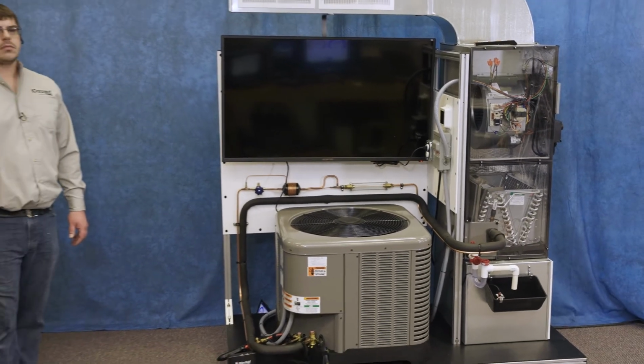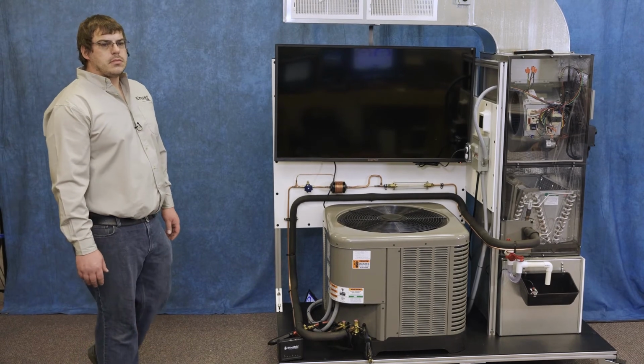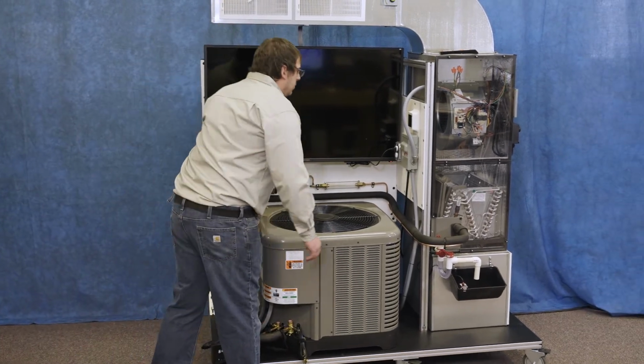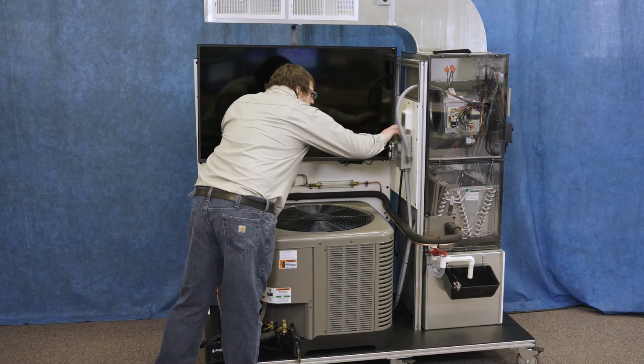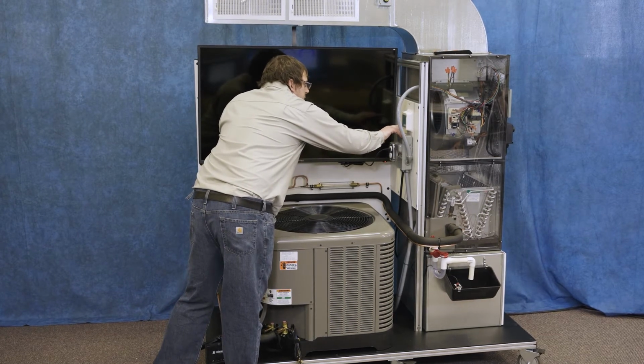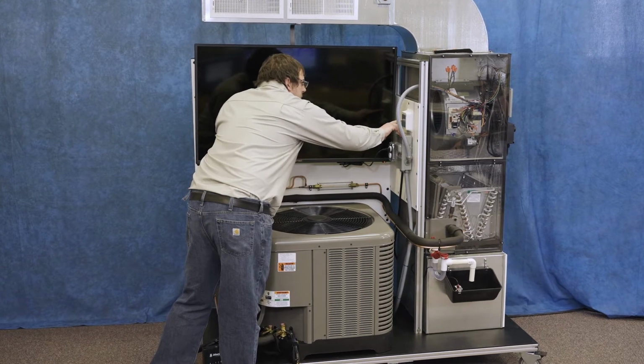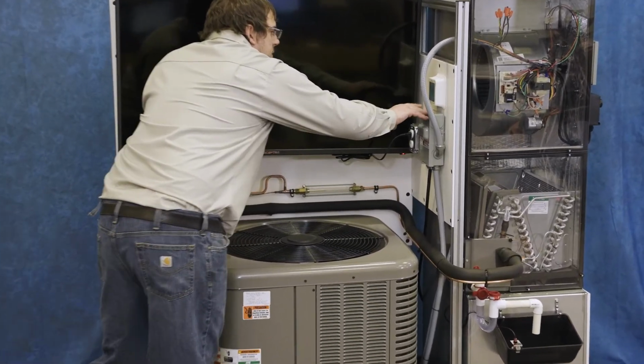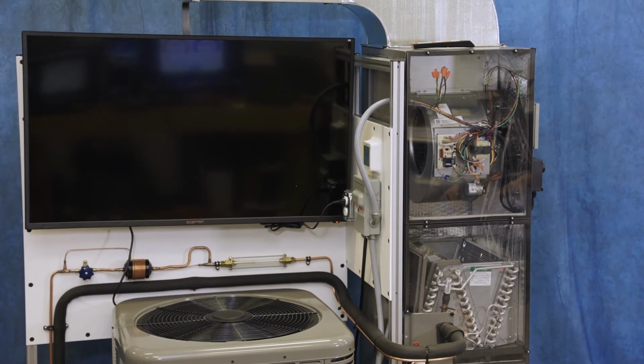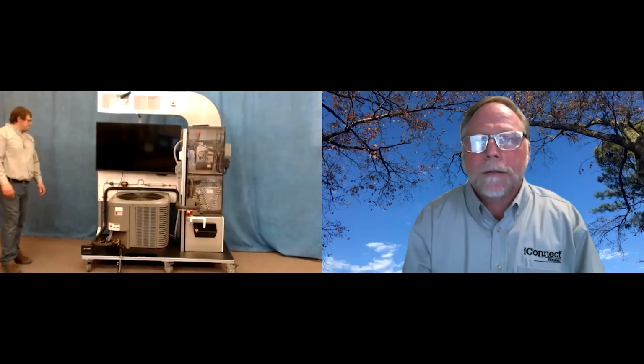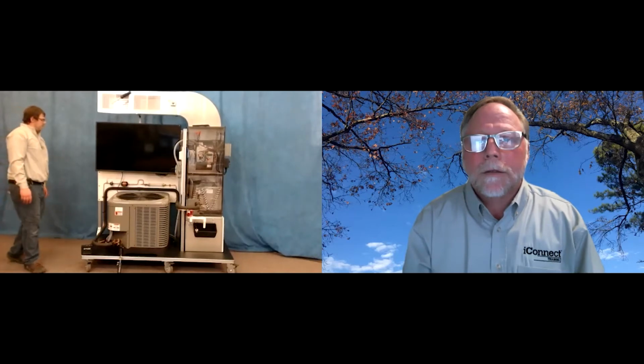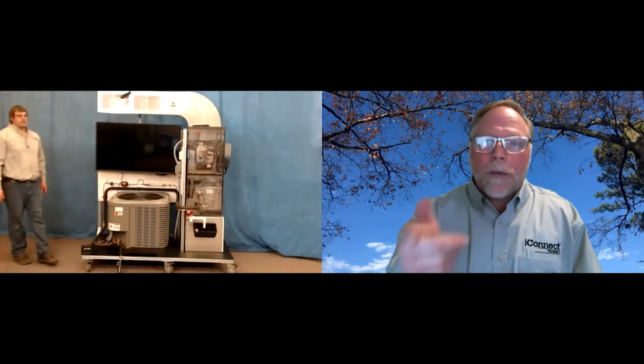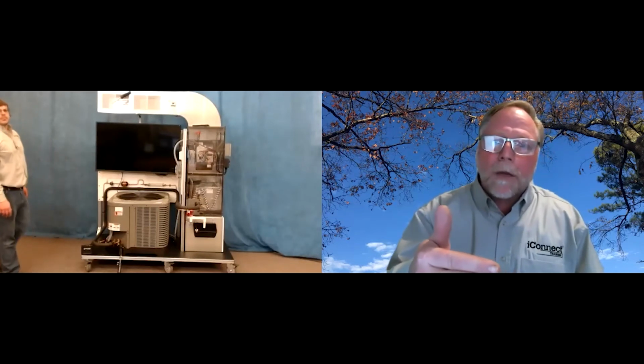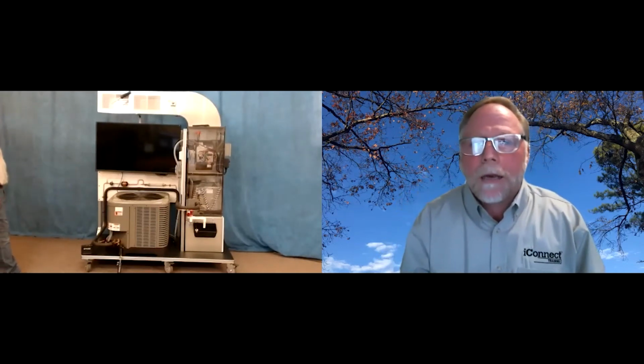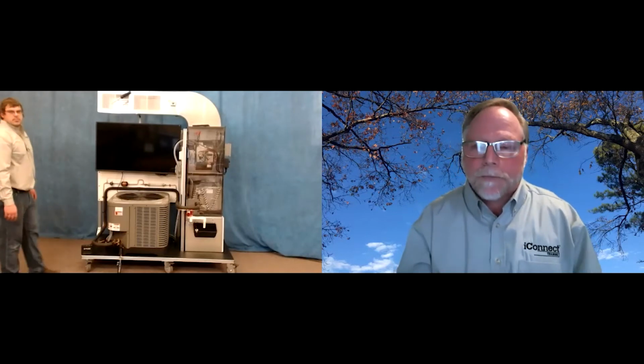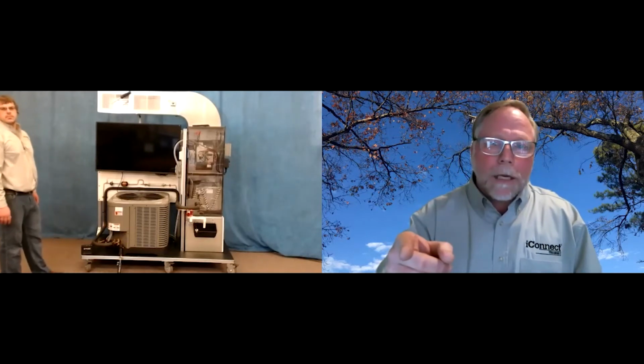All right, Nick, if you would go ahead and go to the T6 thermostat that we have there and put it in the cooling mode. And then go ahead and turn down the temperature so it'll come on, and we'll watch the pressures on the system. All right, there we go. We can immediately see the head pressure going up, the suction pressure coming down. We'll start reading the superheat and the subcooling as it settles out. But we'll let that run just a minute there.